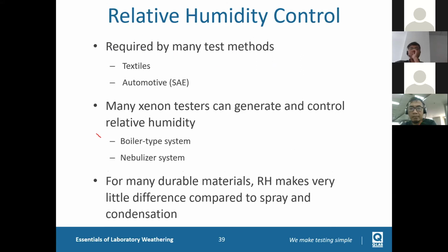The air temperature control is always related to relative humidity control. There are certain test methods that require humidity control, like textile and automotive. They have different types of humidifiers, like the boiler type system, which is our XE3, and the nebulizer system, which is our XE2. But remember, they can both control BP temperature, air temperature, and relative humidity.